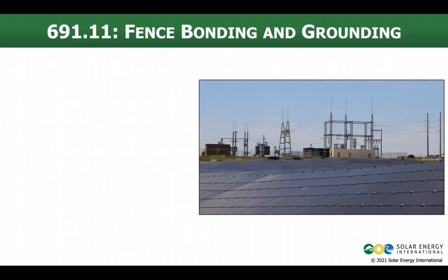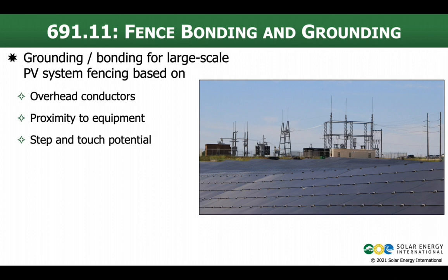We already mentioned that these systems are going to be surrounded by a fence, restricting access to authorized qualified personnel only. Well, we need to consider bonding and grounding that fence because it may be in proximity to energized circuits. So 691.11, fence bonding and grounding. We have to consider proximity to equipment, overhead conductors, and the step and touch potential, the shock hazard that may exist. These have to be considered and documented in the electrical design of the system.